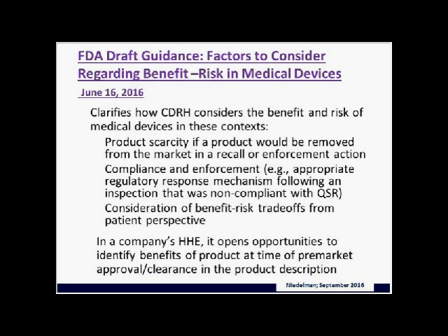Compliance and enforcement, this will be used for both industry as well as FDA in determining benefit-risk associated with the use of a device, a potentially violative device, by both FDA and industry in enforcement actions as well as recall scenarios. And consideration of benefit-risk trade-offs from a patient perspective. If a patient is totally familiar with the use of a device and it means they have to replace it with something else that they're not as accustomed to and might not be as risky, they may take that into account as well. Keep in mind, FDA has historically always looked at these situations as worst-case scenarios.